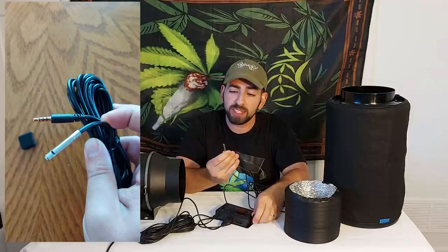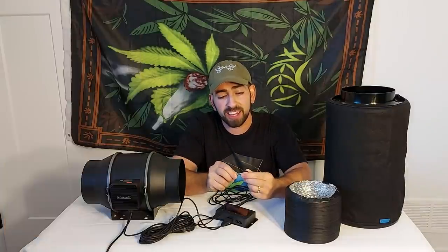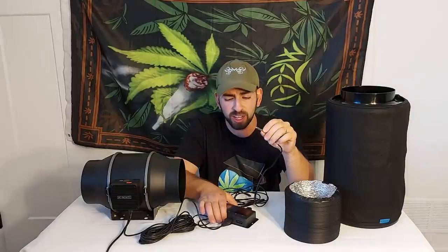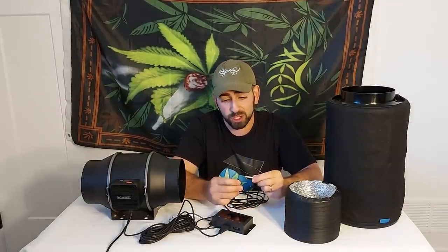It's supposedly a Swedish-made sensor that measures both humidity and temperature, and it's quite sensitive, so make sure it doesn't get damaged. As always, hang sensors at your canopy level — that's where a sensor of this type should be. When I looked into its reliability, I found that while it's generally accurate, there is a reported issue among certain growers that these sensors malfunction in HPS-powered flowering rooms. HPS is becoming rarer, but if you do run HPS, be aware you may get inaccurate readings, leaving you with just basic fan speed controls — in which case the S-series would probably be cheaper.